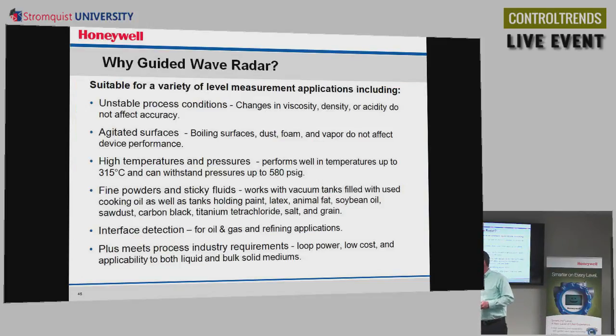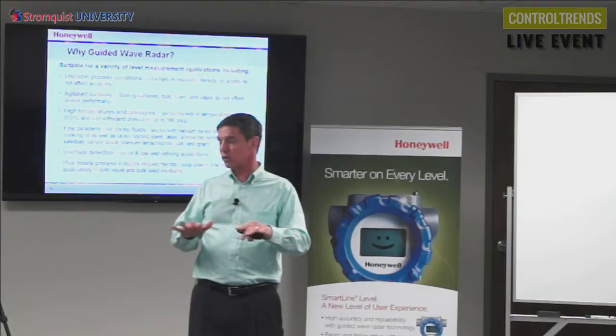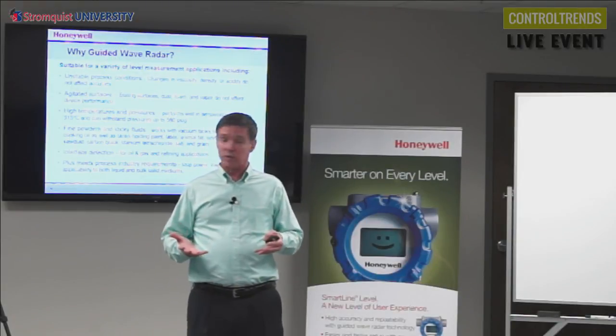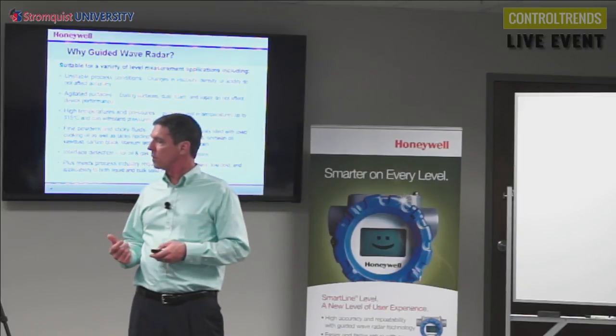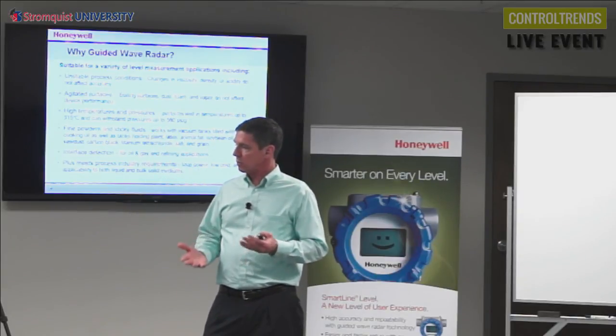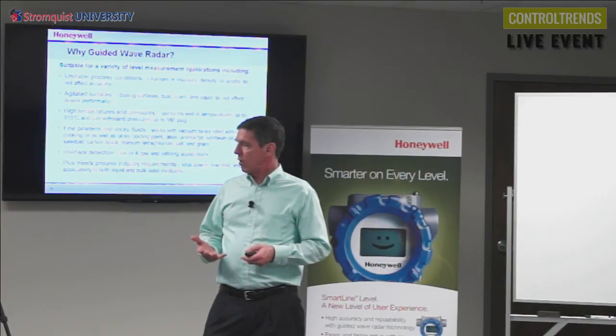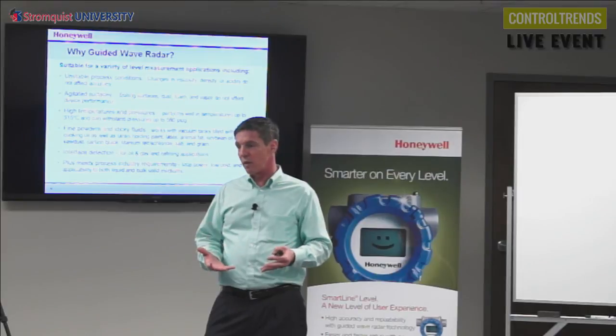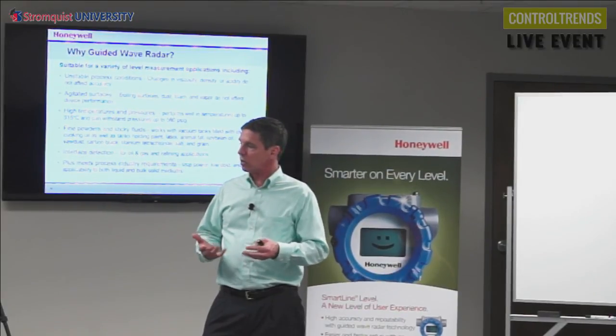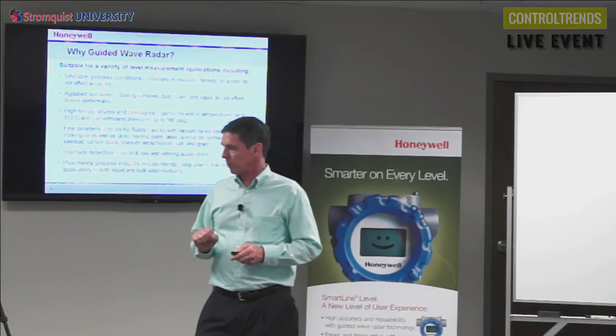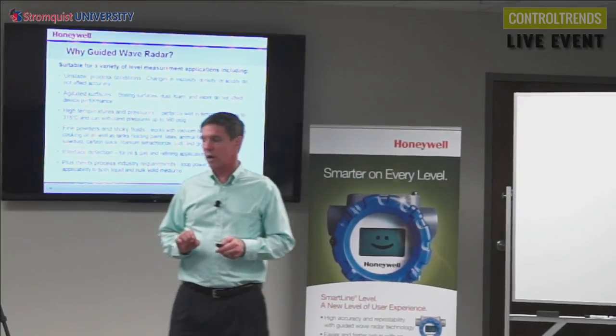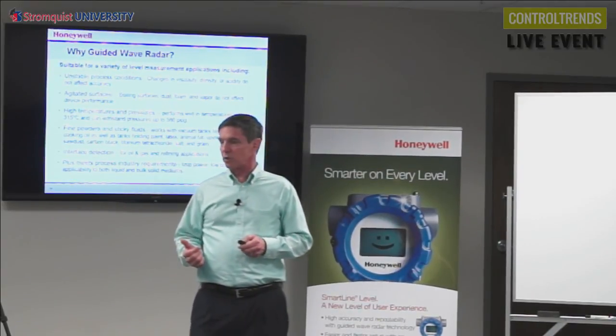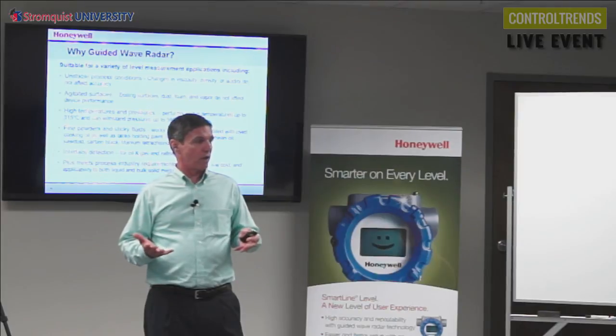And as a summary, why use guided wave radar? What applications? It's really good for unstable process conditions where viscosity, temperature are changing quite a bit, or density is changing. Where you have agitated surfaces, guided wave works well when compared to non-contacting radar or maybe ultrasonic. Works in high temperatures and pressures. We know that some technologies have a limitation with that. It will work with fine powders, sticky fluids. It can work with solids. Sometimes non-contacting is a better way to do it, but it's a matter of really evaluating the application. Interface detection, this is really the best way to go with guided wave. And finally, it meets the process industry requirements for loop power or low power kind of devices.